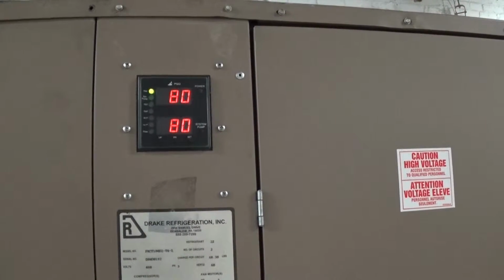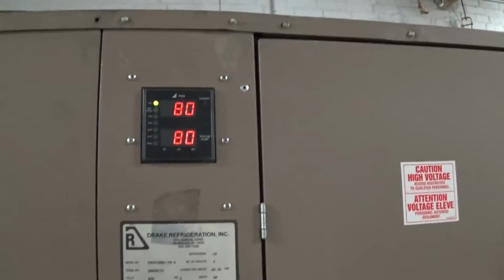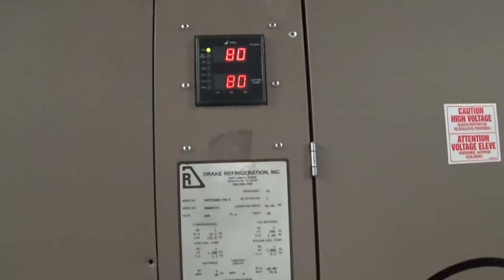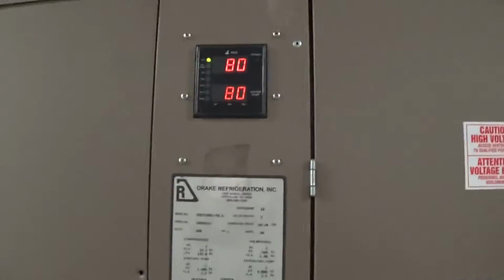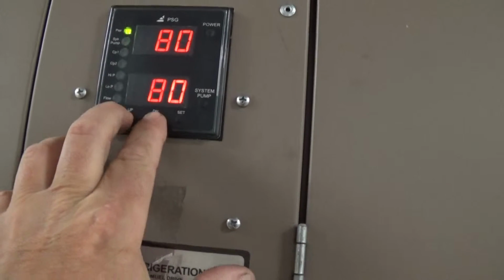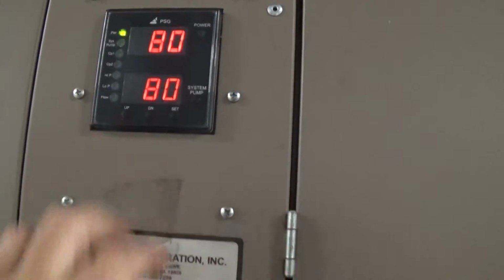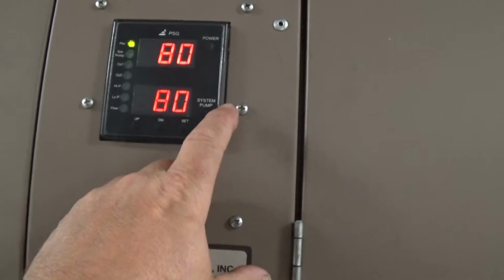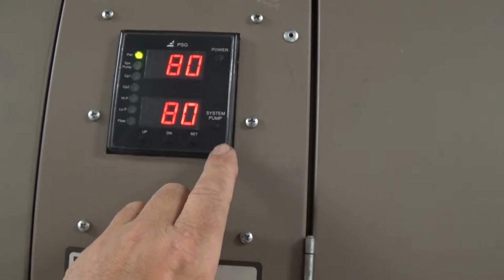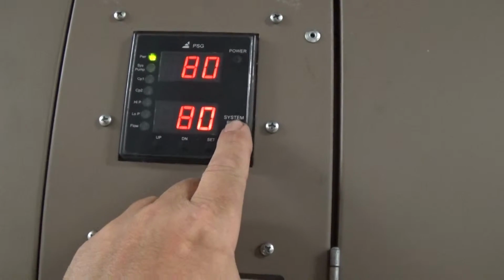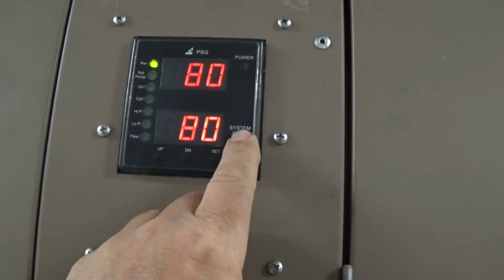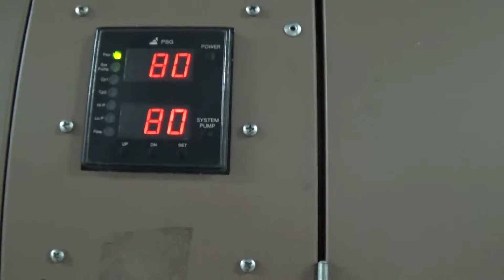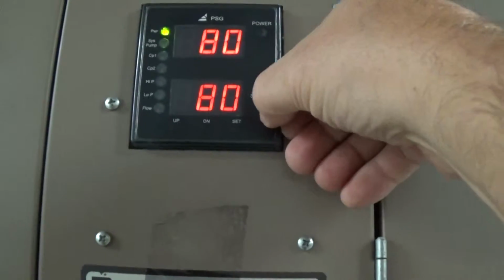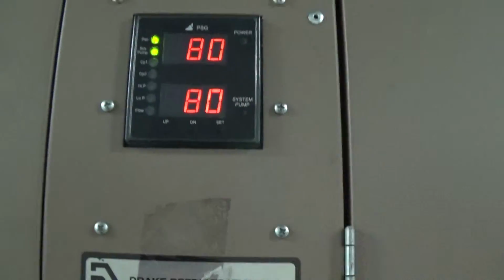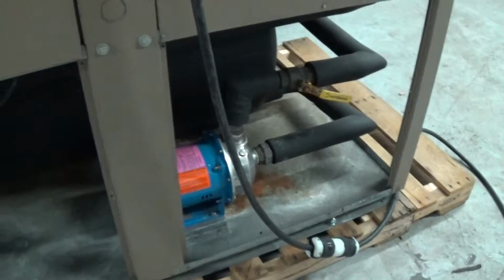To change the set point temperatures, or to get into the program, you actually hold the up and down button in at the same time. But actually, first, what we're going to do is press system pump, the system pump which goes out to your process. That is a separate button right here. And that's what that pump is right there.